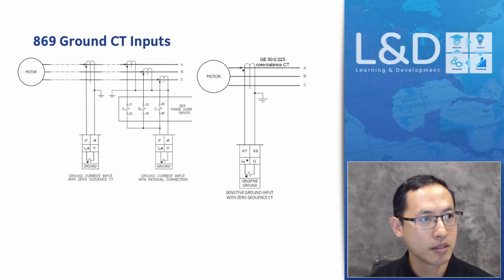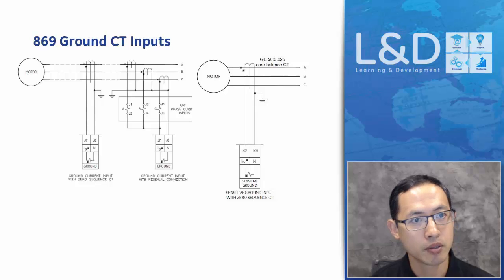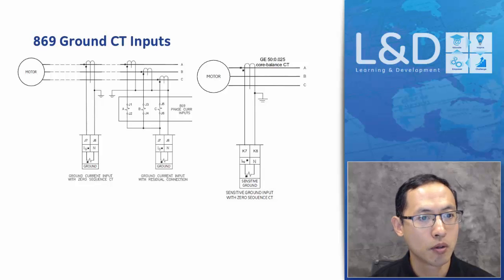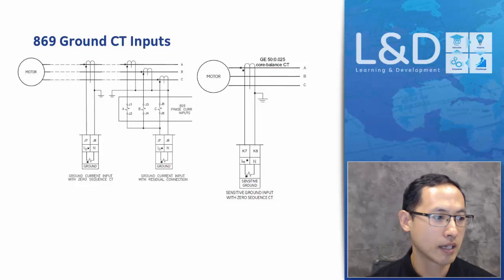For the ground CT of 869, it can be directly connected to the ground, from the zero sequence CTs, from the residual connections, or it can be used as a core balance CT as a sensitive ground input. That will be used for the K slot, K7 and K8.